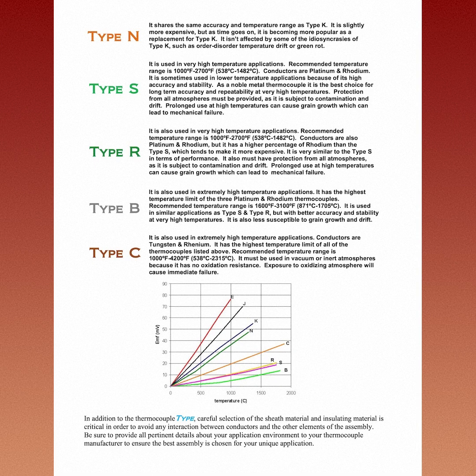Type R is also used in very high temperature applications. Recommended temperature range is 1000 to 2700 degrees F or 538 to 1482 degrees C. Conductors are also platinum and rhodium, but it has a higher percentage of rhodium than the Type S, which tends to make it more expensive. It is very similar to the Type S in terms of performance. It also must have protection from all atmospheres, as it is subject to contamination and drift. Prolonged use at high temperatures can cause grain growth, which can lead to mechanical failure.